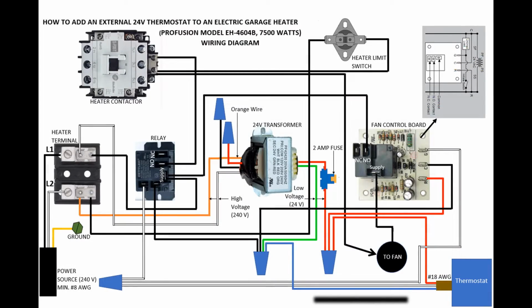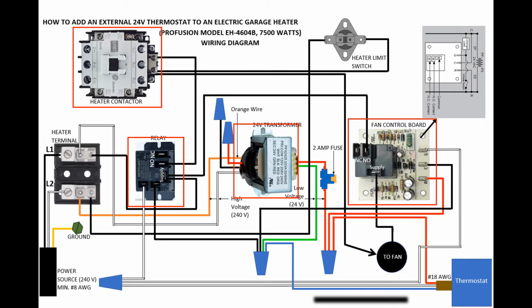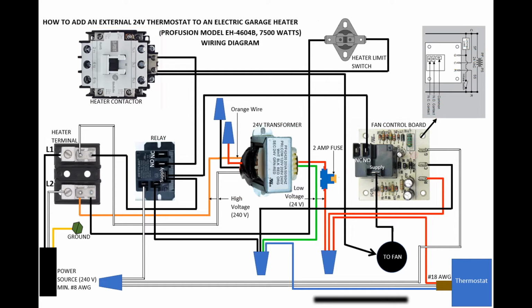Now let me show you how we're going to rewire this heater. Here's a wiring diagram that I drew. Here's the contactor, here's the relay, the step-down transformer, and here's the fan control board or fan timer. Let's start at the power source. So you have 240 volts of electricity coming in using a number 8 gauge Romex wire, which is connected to the L1 and L2 of the heater terminal as shown here. And the ground wire is connected to the green ground screw in the heater.